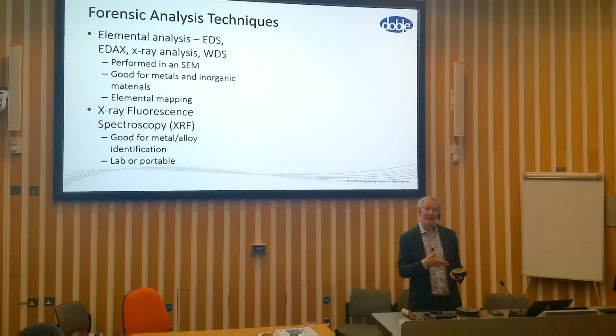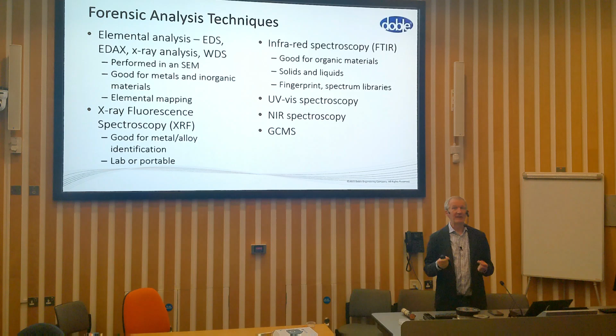And if it's an organic material, a plastic, a grease, an oil, then we're going to use some kind of spectroscopy usually. Infrared spectroscopy, UV, gas chromatography, mass spec. And these will tell you what the molecules are. So again, if you have an unknown contaminant, not so much with cables, but in the case of transformers, there's been issues in the past where people have used the wrong grease. It attacks the seals. But you then need to prove which is wrong. Is it the wrong seal that's been used or the wrong grease that's been used? Sometimes people have put the wrong oil into transformers or into a cable termination, in one case I was involved in. So again, being able to identify it and prove it is valuable.